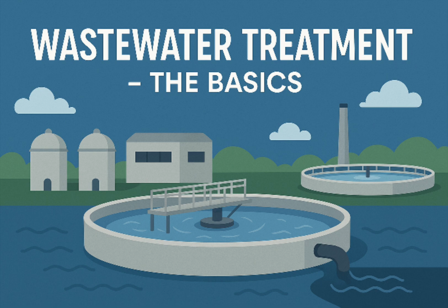Yep, sedimentation tanks or primary clarifiers. Here, the water slows down even more. And this allows the suspended solids, tiny bits of organic and inorganic matter, to just settle out by gravity. This forms a sludge at the bottom. We call it raw primary biosolids. And what about stuff that floats, like grease? Right, lighter stuff like fats, oils, and grease floats to the top and forms a scum layer. So you're basically separating things that sink from things that float. And then what? Skim the top, pump the bottom? You got it. The scum is skimmed off, the sludge is removed from the bottom, usually pumped out, and the water that's left, which is partially treated now, moves on to the next stage.